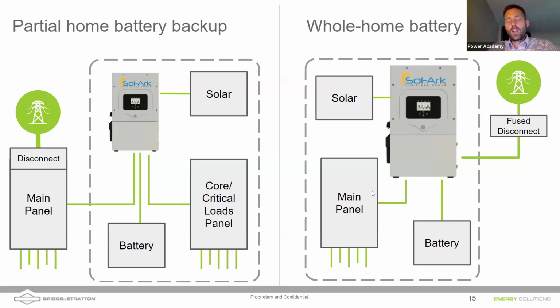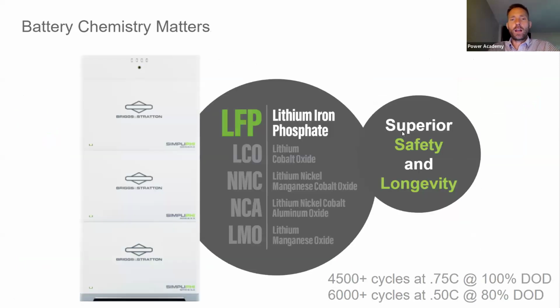And we can talk about, there are some clever ways to do this. So if during a grid down situation, you don't want to run the pool pump or the spa heater, etc., you could run that off of a sub panel that's fed out of the smart loads port on the Sol-Ark or the Gen port. So you can use that as a smart loads port and dump some of those loads in a grid down situation. Again, we're bringing our solar into the Sol-Ark. If you do have AC coupled solar with microinverters, the Sol-Ark is capable of keeping those alive in a grid down event as long as you've got a battery to run that Sol-Ark off of. So this is whole home backup.